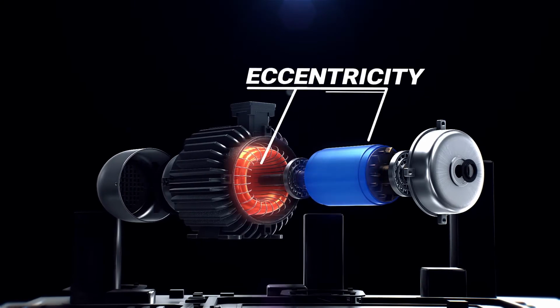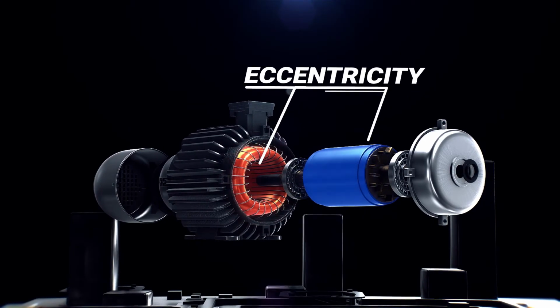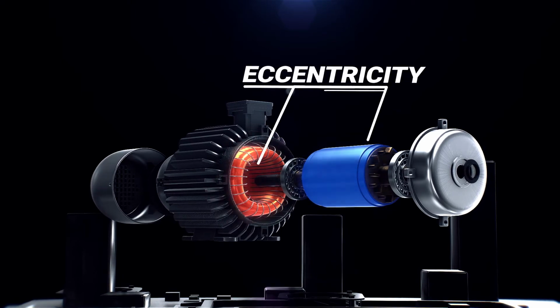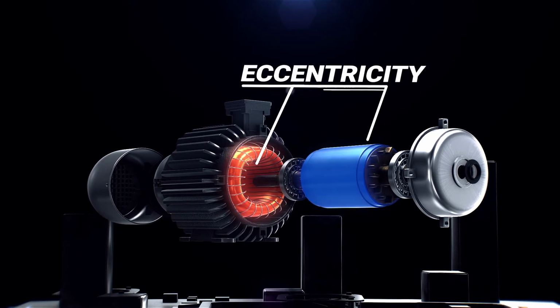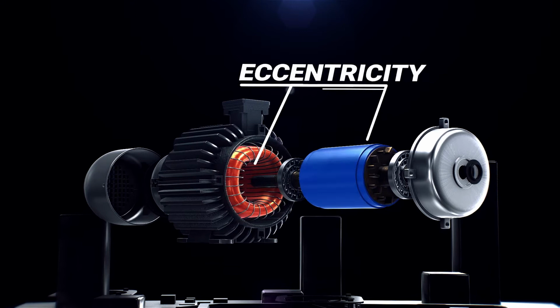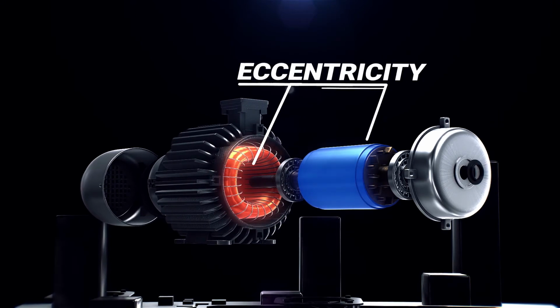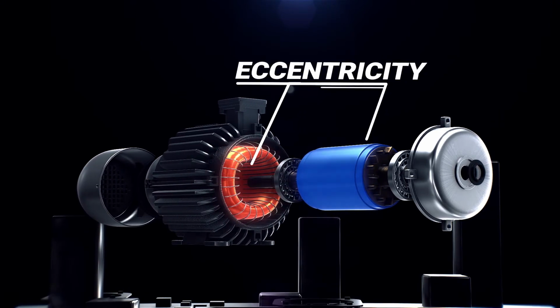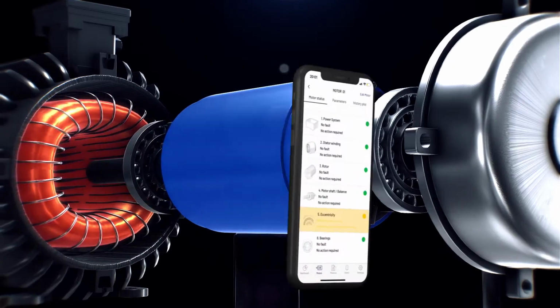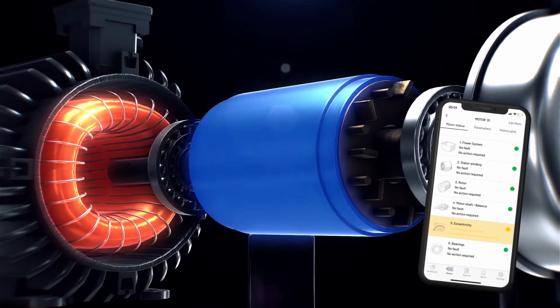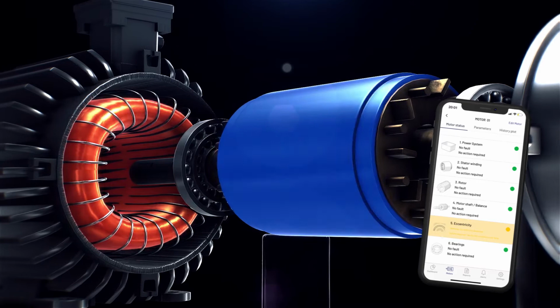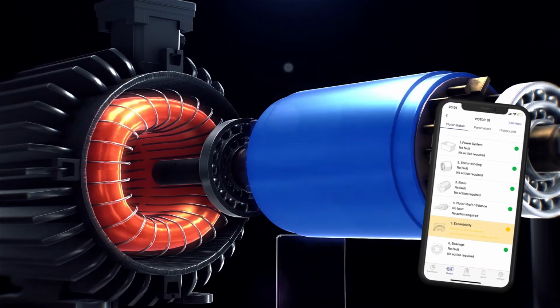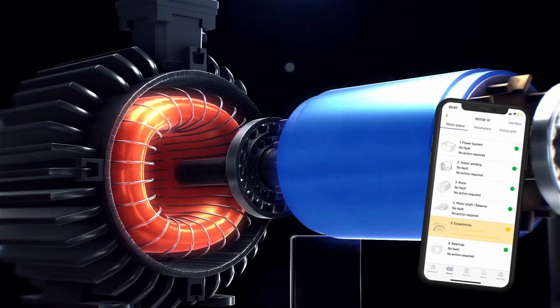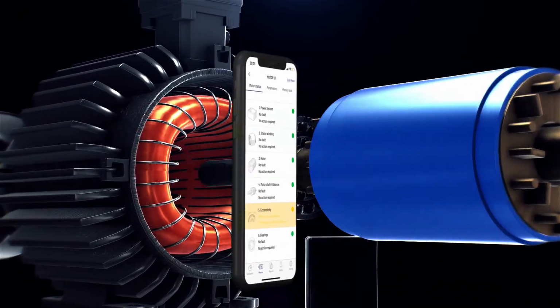Eccentricity. It refers to a mechanical or electrical irregularity. Eccentricity is defined as the offset between the axis of rotation and the axis of symmetry. It can take place in the relative positioning between two concentric pieces, like the rotor and the stator of an electric motor. A faulty installation of the bearing creates internal alignment problems in the motor. The gap between the rotor and stator can change due to a bent axis.